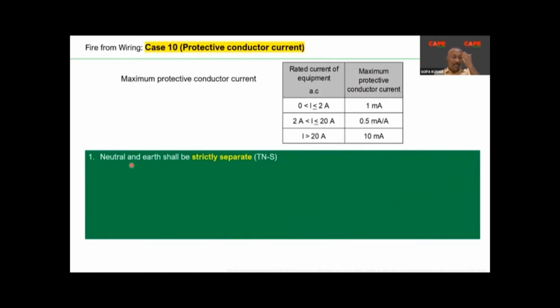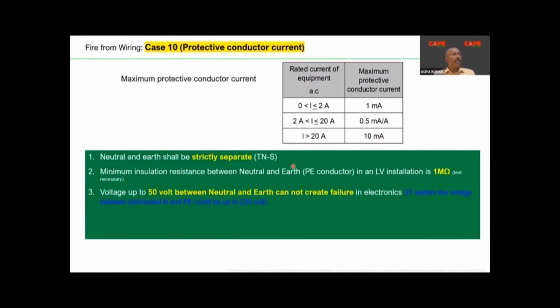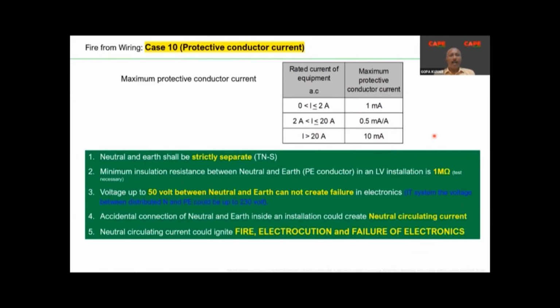One of the important safety measures which has to be taken care of in a hospital is the PE conductor current. Very simple to understand. The earth wire is supposed to be a dead wire. No voltage or current flow must be allowed in that particular wire. But because of the inherent characteristics of electrical equipment, sometimes there will be a leakage current flow, but the system must be designed and tested in such a way that the leakage currents are regulated or reduced to less than the allowable limit. I just took one case. The maximum leakage current or continuous current flow through the earth wire is 10 milliampere. If this current is exceeded, then you will have problems of fire and unwanted sparks in some locations. This will create a safety hazard.